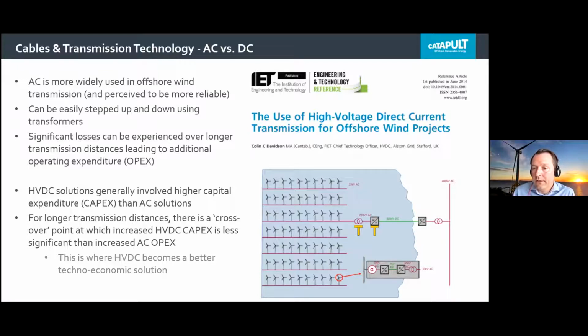But the main drawback, particularly when your wind farm is transmitting over a further distance from shore or from the collection point, is that there are significant losses experienced over those long cable distances, leading to additional operating expenditure because you've effectively got to boost the voltage along the way. That's where HVDC solutions become a little more attractive. The drawback to HVDC is that capital expenditure is generally higher than AC, but over a longer transmission distance there's a crossover point where the increase in capex of HVDC is outweighed by the increased operational expenditure of the AC solution. That's when HVDC is sometimes seen as the better techno-economic solution. So that's essentially the consideration involved.